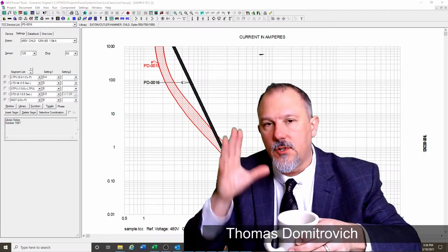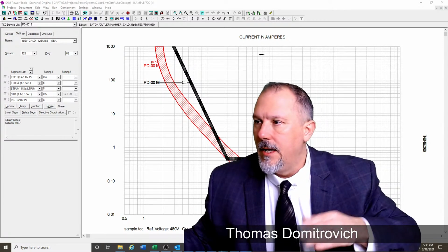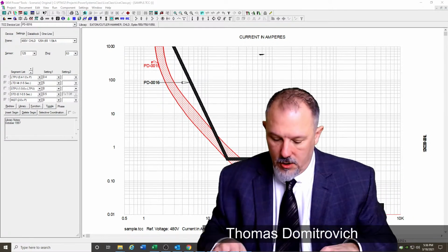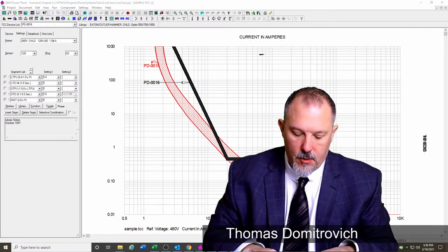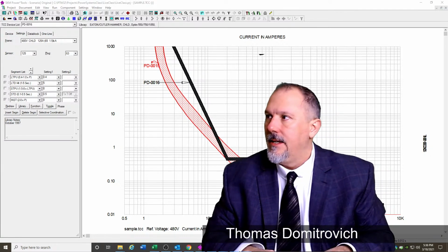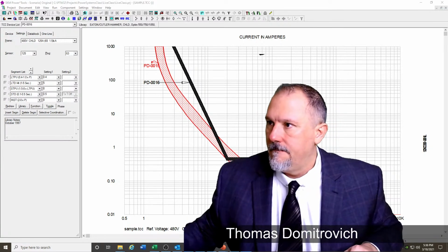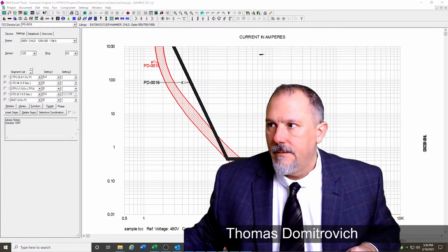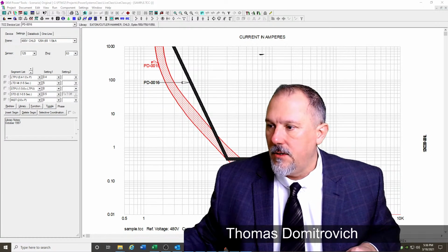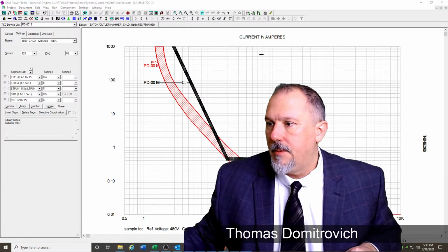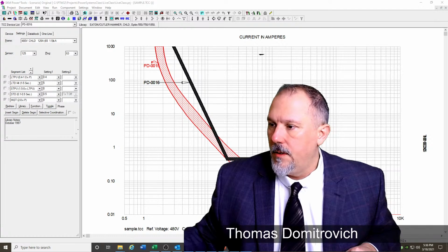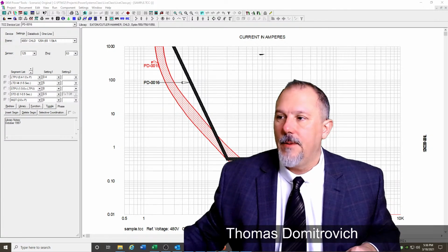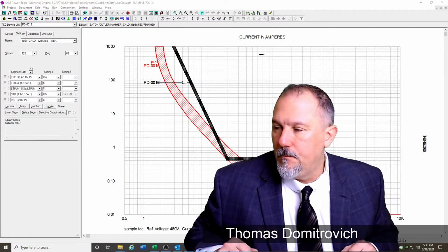I can't show it because it's copyright information, so I'm going to read it to you. Control F, and I'm looking for Instantaneous. Okay. Instantaneous trip circuit breakers. But up here's the scope. Instantaneous trip only. Here we go. Instantaneous pickup.